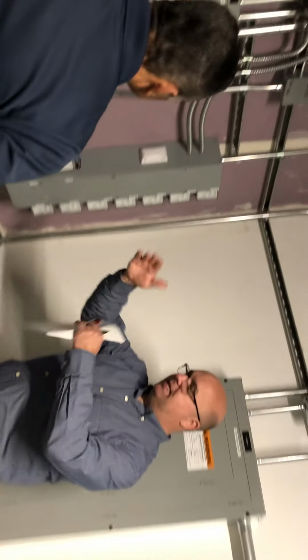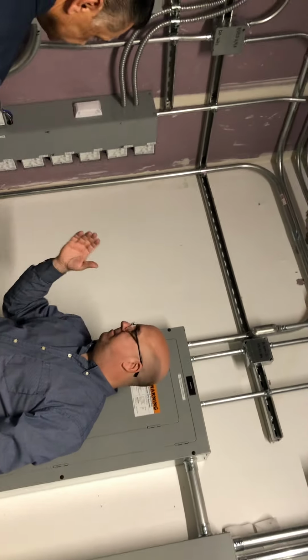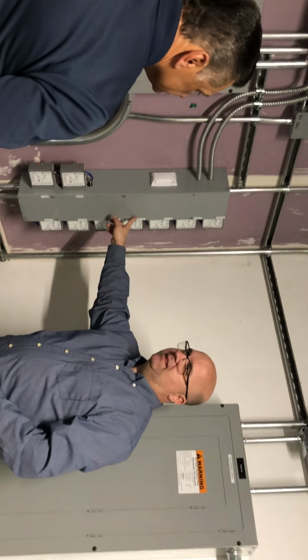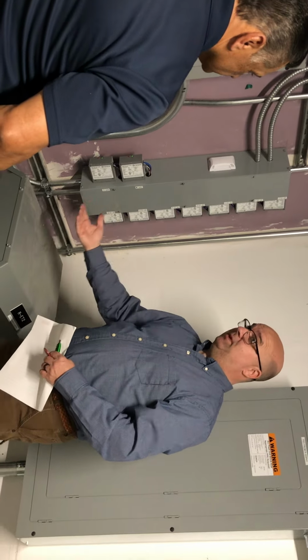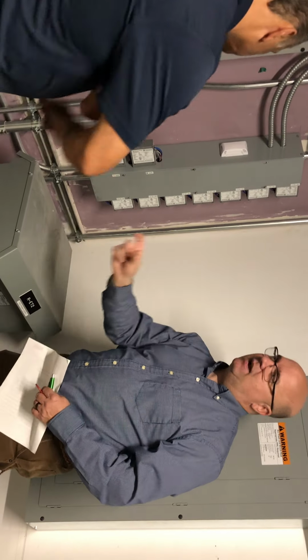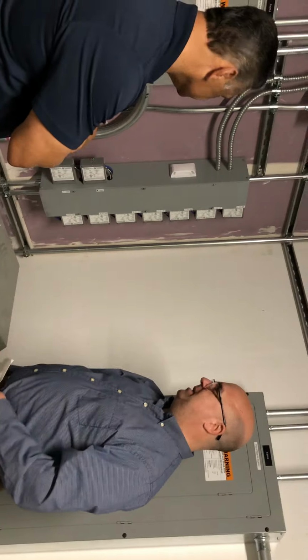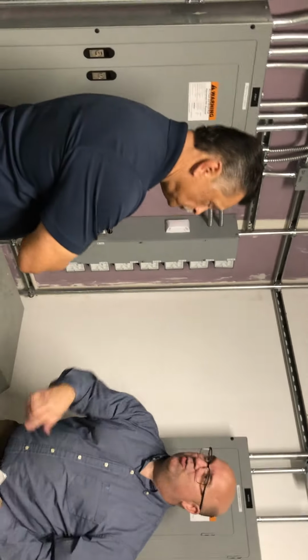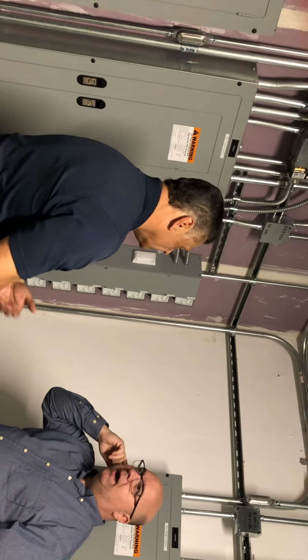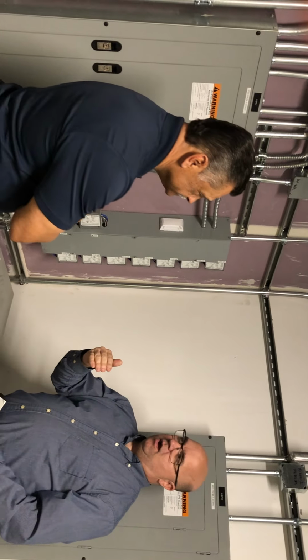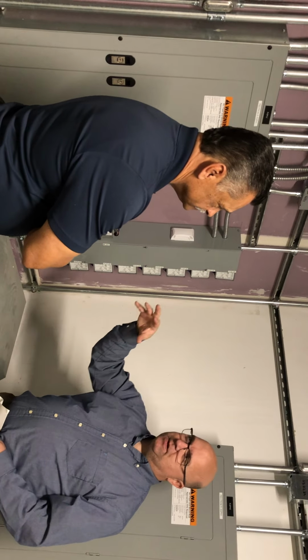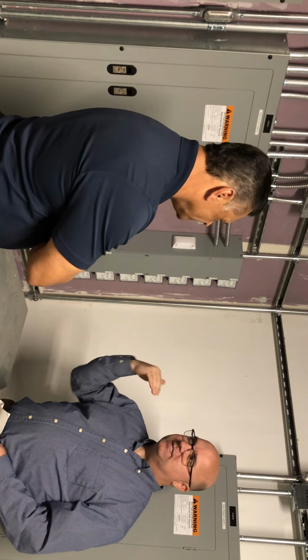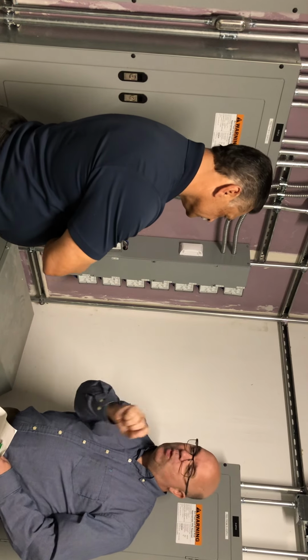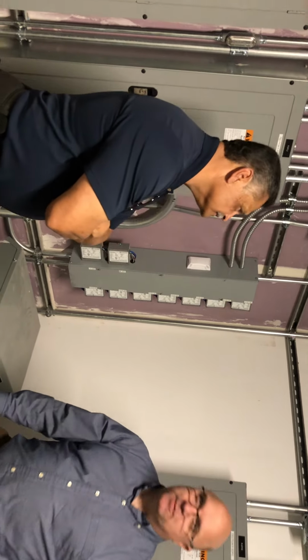More exhaust fans, and you'll see a table we're building, because to you, EF12.2 doesn't mean anything. You need to know what area of the building it serves, so we're building a table listing that out. If somebody says supply fan 16.1, that doesn't mean anything to you, but you need to know what area it serves. That way, if a portion of the building seems stuffy, or these corridors seem off, you can look and see what equipment serves that particular floor.